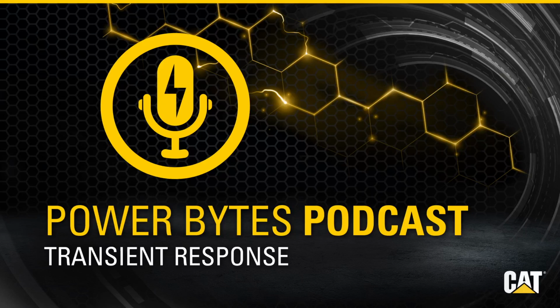What this means is that we're looking for a system that is receiving power from an external source to support their excitation. So this would be something like a permanent magnet or an internally excited generator from Caterpillar. Having these external sources for excitation energy allows the generator's voltage to recover faster during a transient.